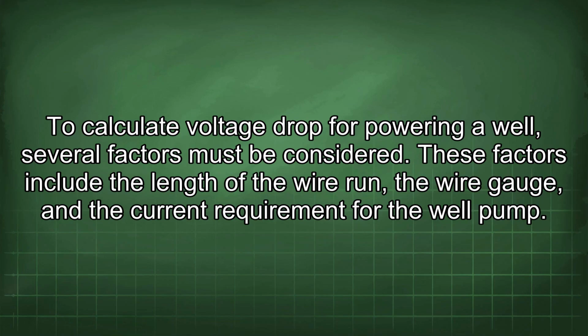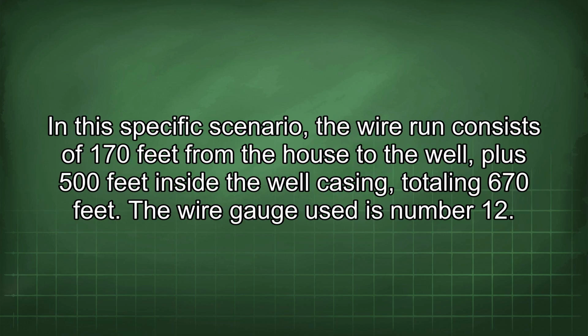To calculate voltage drop for powering a well, several factors must be considered. These factors include the length of the wire run, the wire gauge, and the current requirement for the well pump. In this specific scenario, the wire run consists of 170 feet from the house to the well, plus 500 feet inside the well casing, totaling 670 feet.